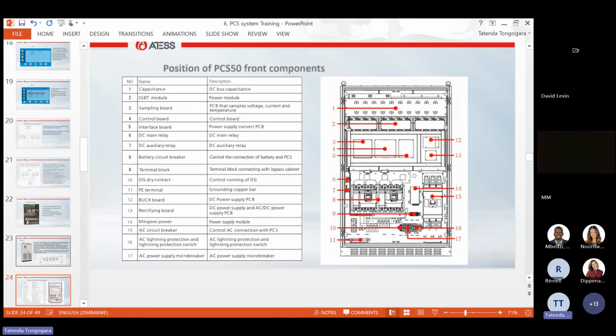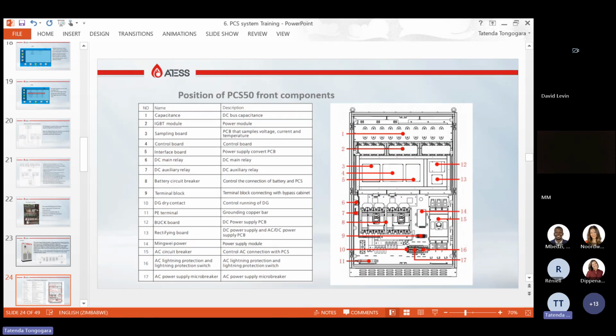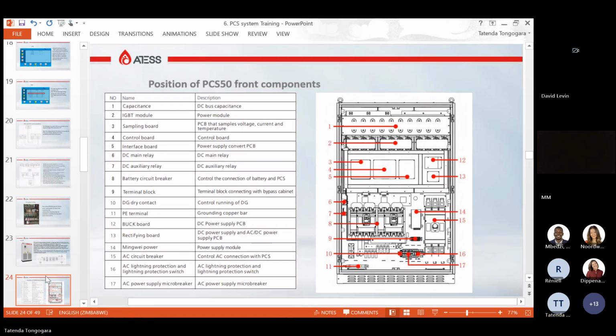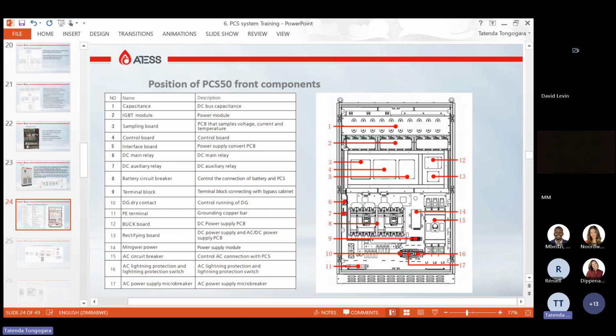So this is how our HPS, the PCS, looks like inside. These are our capacitors, the DC bus capacitance. This is the control board, the relay, and the sampling board. And then we have the DC breakers here. And then we also have the dry contact relay where you can start and stop your generator. That is number 10 here. And then you have your output here.